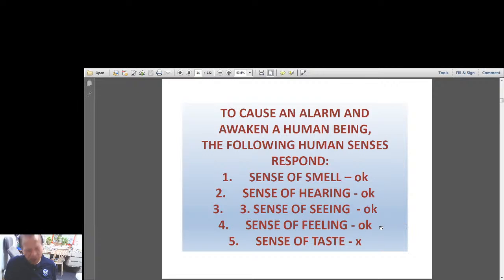The sense of feeling is not yet there, but we have already suggested it, and that is by the use of smart watches, mga relos, that have the capacity to vibrate. The smart watch must have a SIM card inside, so that in case of a fire, the programmable logic control or the fire alarm control panel, which is a computer, will send a signal to the SIM card of your smartwatch, and the smartwatch will vibrate, and therefore it will affect the sense of feeling of an individual, for him to be awakened. So as of today, inside the burning room, you have the sense of smell, then the sense of hearing is part of the FDAS today, and the sense of seeing is also part of the FDAS because of the alarm light, the rotating beacon, and the LED lamp.